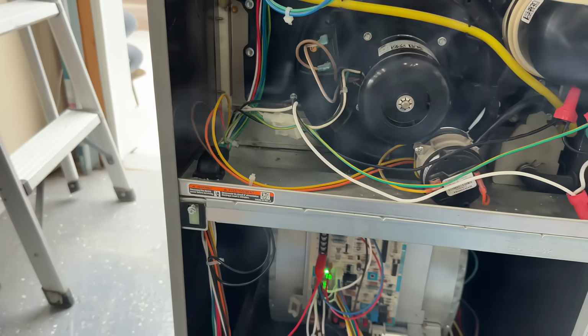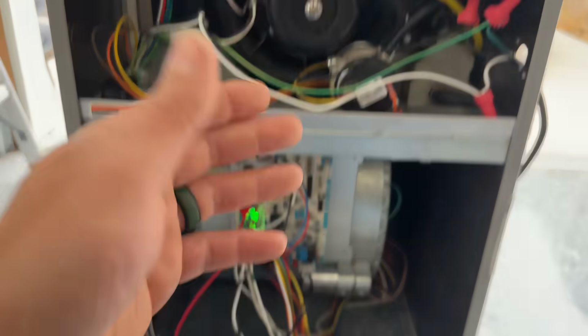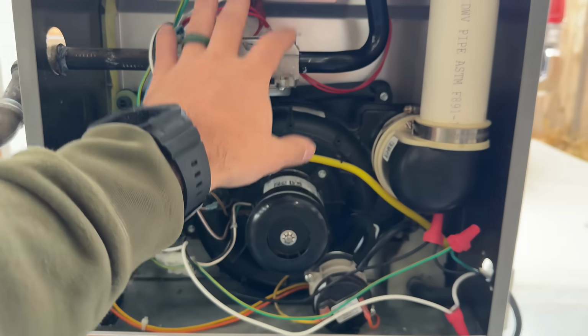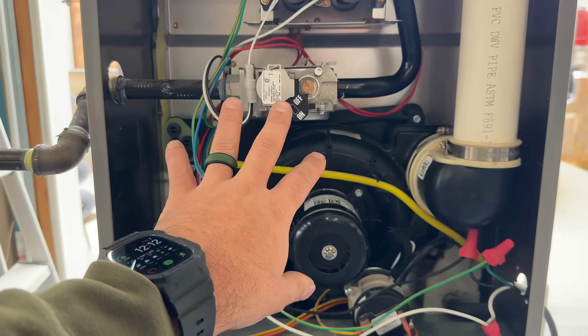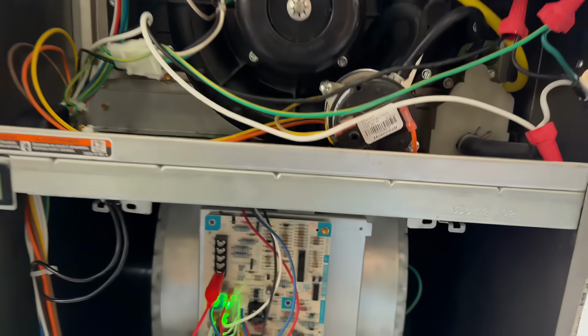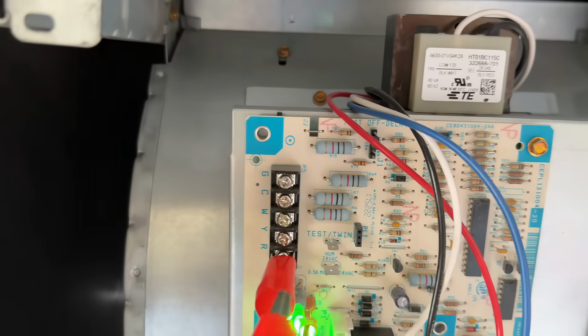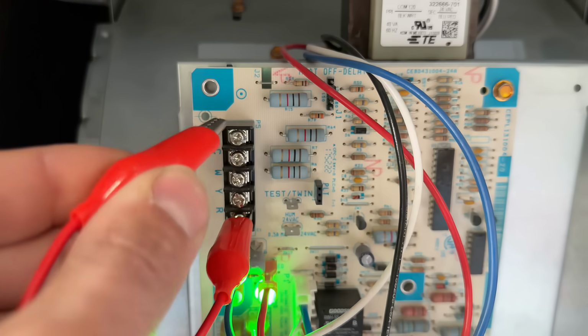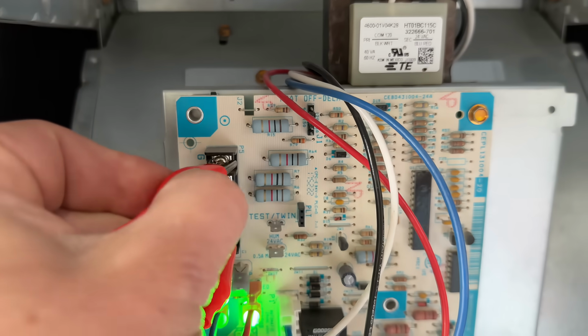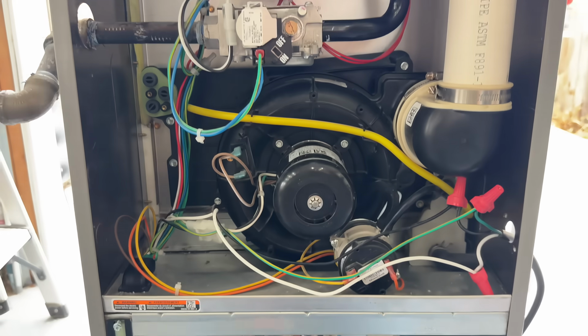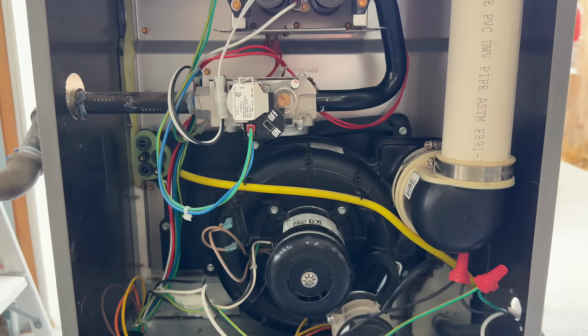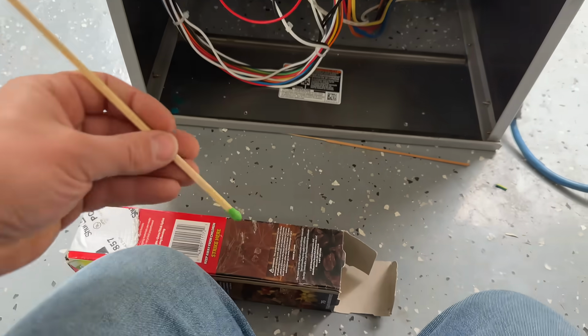So what we're going to do now is we're going to turn the blower motor on and do this same test. So we don't need to activate anything with the combustion side. So all we're going to do here is we're going to jump the R terminal and the G terminal. Or if this was in your home, all you would need to do is go to the thermostat and just put your fan in the on position. So we're going to do the same test here.